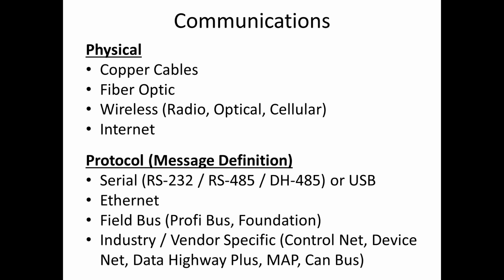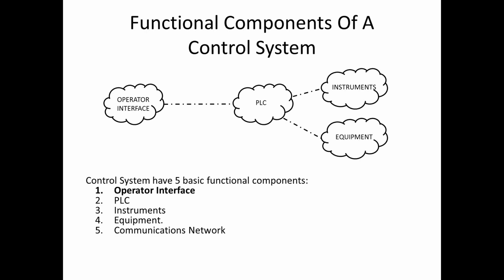There are some industry and vendor-specific protocols that can be used, and there are actually different types of field bus, Profibus and Foundation. Those are all different ways that messages actually get transmitted across the communications network. The other part of this is that the instruments and the equipment all get transmitted through the PLC, and the PLC can take that information to the operator interface.